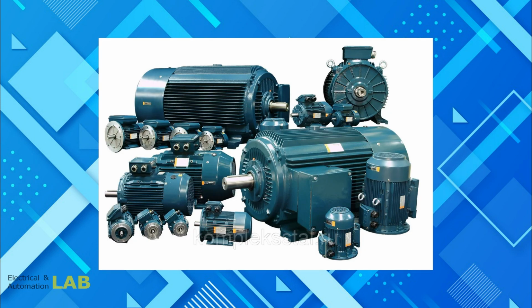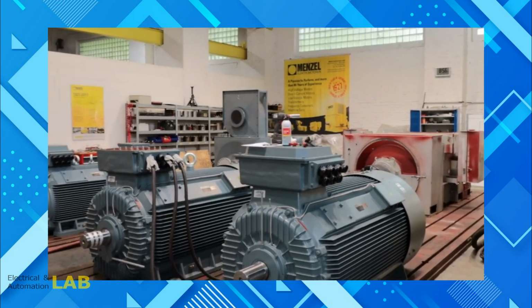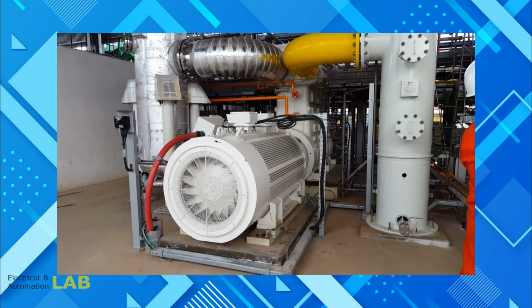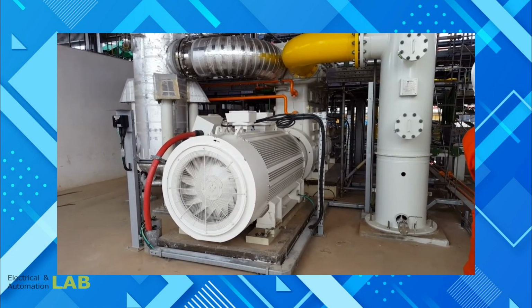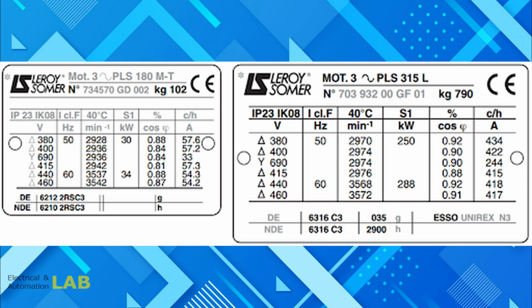So how to connect an electric motor so that it works for a long time and serves you faithfully. First of all, we need to look at the nameplate of the electric motor, on which all the main characteristics of the electric motor are written. We are interested in current, voltage, connecting the windings. Well, the frequency of the network, in my region is 50 Hz.